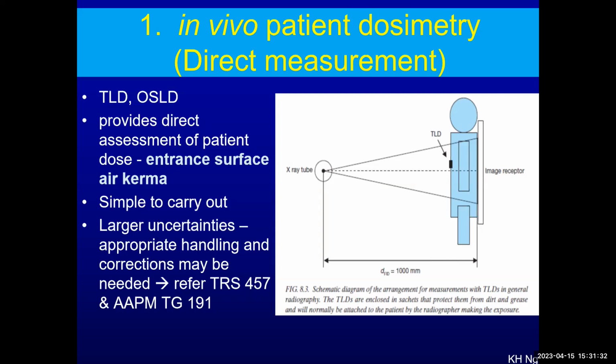focus detector distance, right? It's relatively simple to carry out. In the past, TLD is laborious. You need to cool down and anneal, right? But OSLD is more like instantaneous.